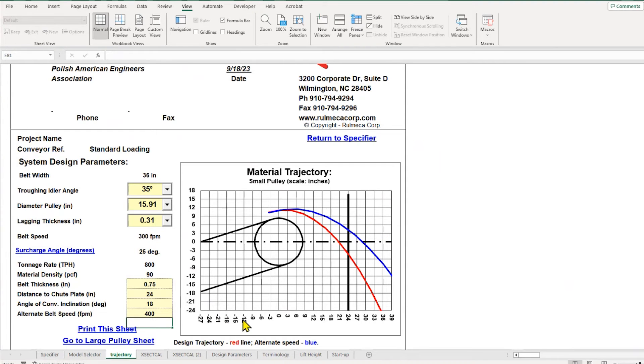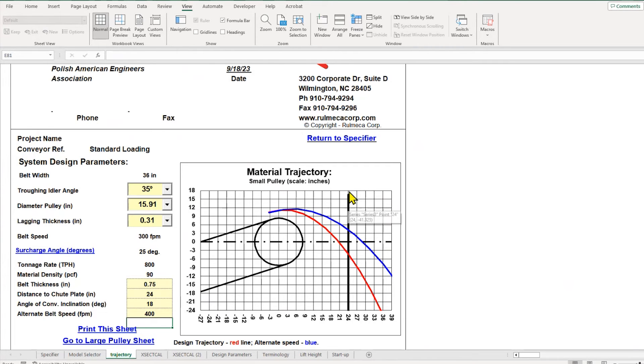And you can see that this is showing that to speed up this conveyor would cause a problem if the chute—this black line represents the chute—is 24 inches from the center line of rotation of the pulley.